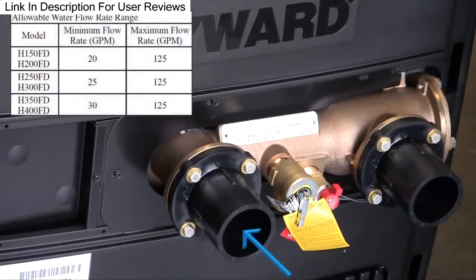The minimum allowable water flow rate, shown on the screen and in your installation manual, varies depending upon the heater model. The maximum flow rate is 125 gallons per minute on all heaters. If your pump and filter normal flow rate exceeds 125 gallons per minute, an external bypass must be installed. Damage caused by flow rates outside of the allowable limits is not covered under the warranty.